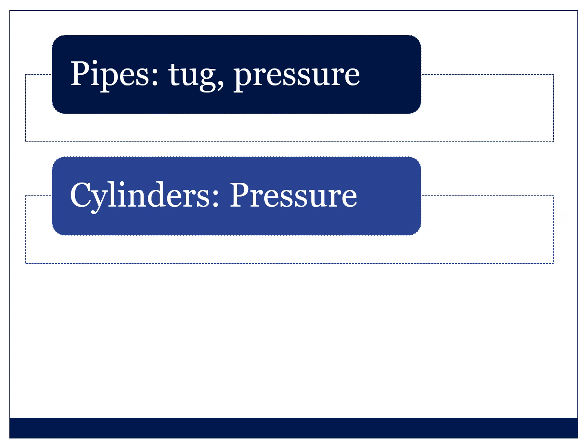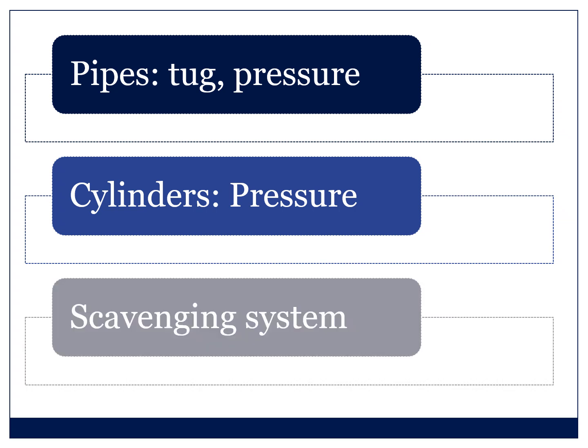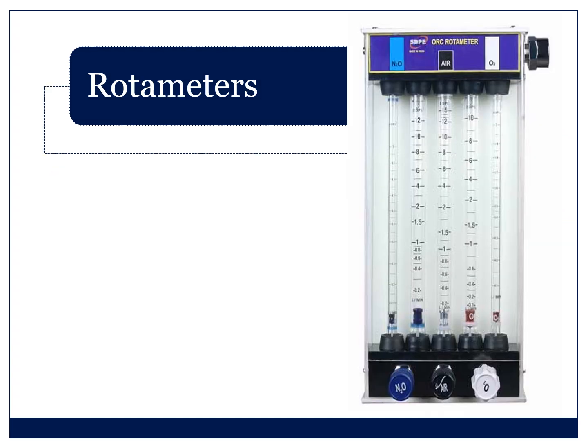Then you go to your cylinders. We've talked about doing the oxygen cylinder already. You check your cylinder pressure, and finally you check that you've got a scavenging system. Following that, you should check your rotameters. Now, not all machines have rotameters. Some of them have electronic ones. Most of the district hospital ones do, and there's usually nitrous, air, and oxygen. And these rotameters should open easily. They should rise adequately. The bobbins should rotate and not stick. And when you occlude the fresh gas flow, the bobbins should bounce. And you should actually repeat that test with the vaporizer open and with it closed. It's one of the things that tells you there's no leak inside your machine.